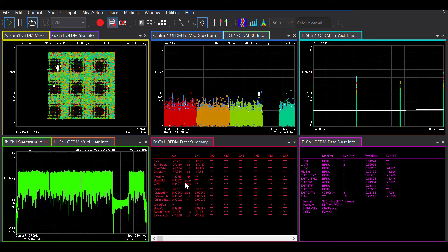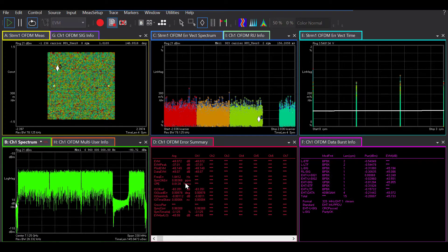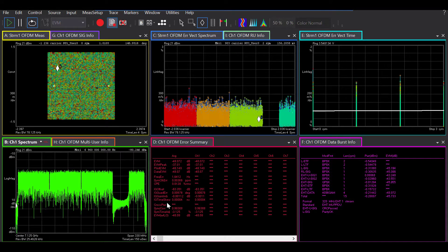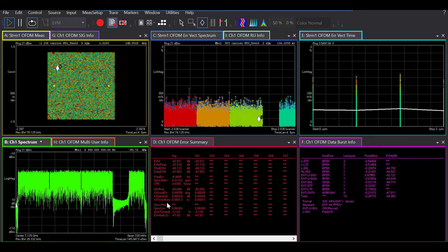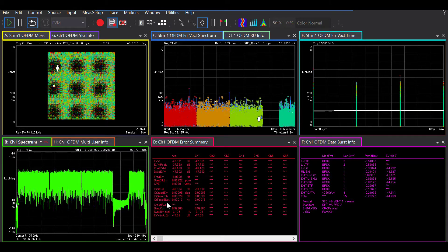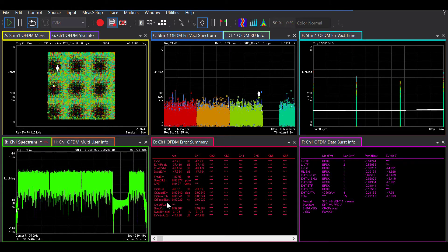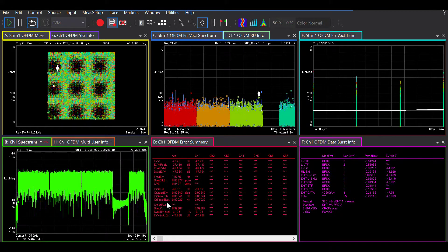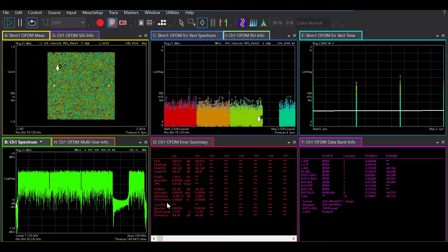The next one is your error summary table, which shows you the results of each input channel. It includes lots of information, for example your EVM, frequency errors, IQ offset, power, and more. I have explained all of these parameters in detail in my other demo videos, and I will include a link for those of you who are interested. For today, all of these parameters are great hints — if anything is wrong with the quality of your signal, such as the quality of your phase component, amplitude components, or if there are any errors in your RF frequency or LO frequency, this will show up on these different parameters in this table.